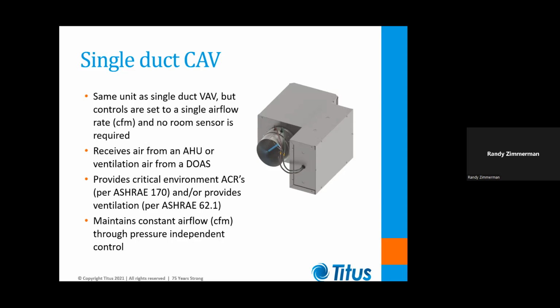Or we can create an isolation ward where we keep the room under negative pressure, and that holds whatever's in the room so that it doesn't contaminate surrounding spaces. So that would be like a patient with a highly contagious disease or something like that. And of course, we're going to have to get the right number of air changes per hour in order to meet the requirements of ASHRAE standard 170, which is the healthcare standard.